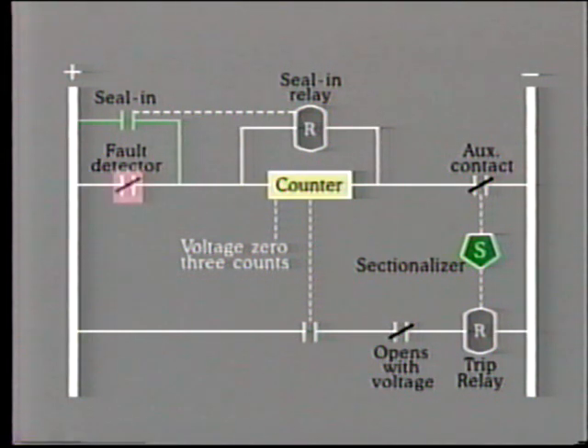The high current flow detector starts the counter. But remember, this circuit is going to be interrupted 3 times. So we need a seal-in circuit here in order to make sure that the counter is not interrupted. After 3 counts of 0 volts, the associated contacts close on this branch, and providing the voltage is 0 on the line, the trip relay will be energized. This is a normally closed contact that will be held open as long as voltage remains on the line.